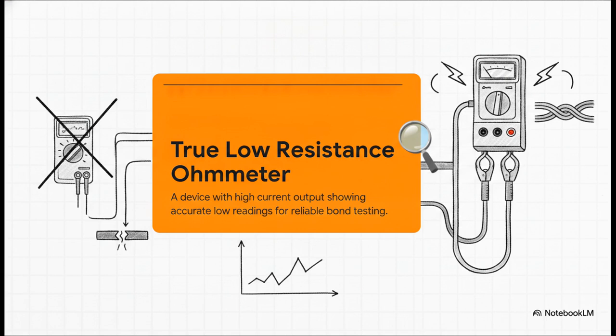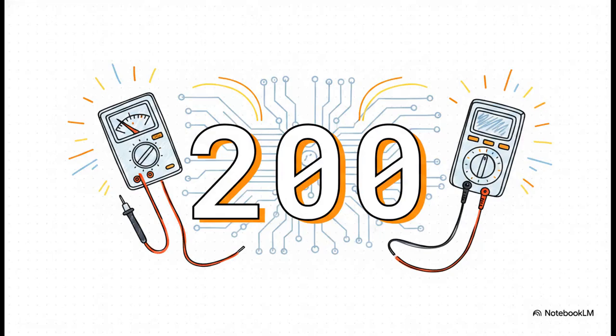You need a true low-resistance ohm meter, one that's capable of accurately displaying readings between 0.01 and 10 ohms with a high current output. That right there is exactly what we mean by high current output. 200 milliamps. That is the recommended minimum test current for your low-resistance ohm meter, whether it's an analog or digital meter. Pushing at least 200 milliamps through the circuit during a test is what simulates a real-world load closely enough to reveal if a connection is truly secure or if it's just barely hanging on by a thread.